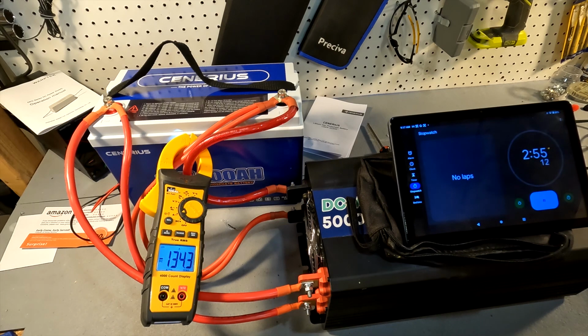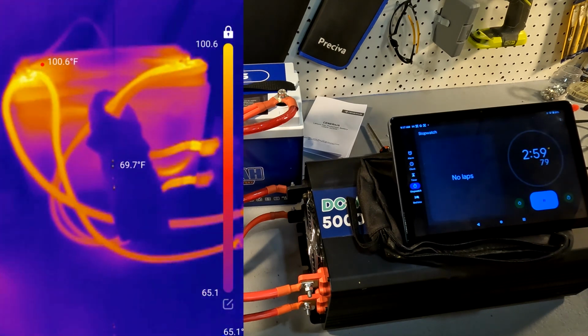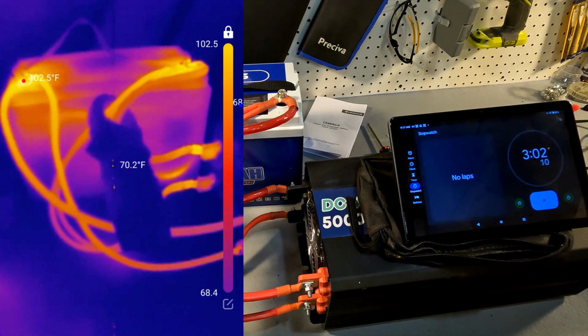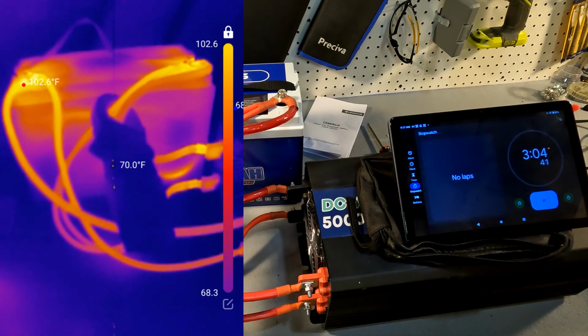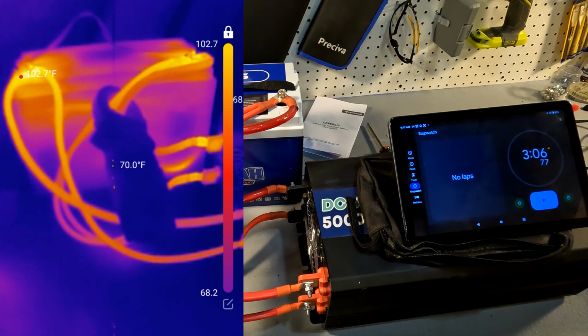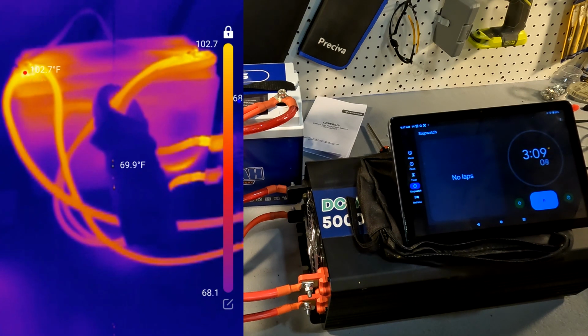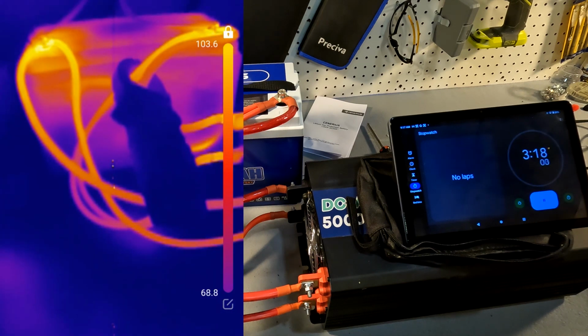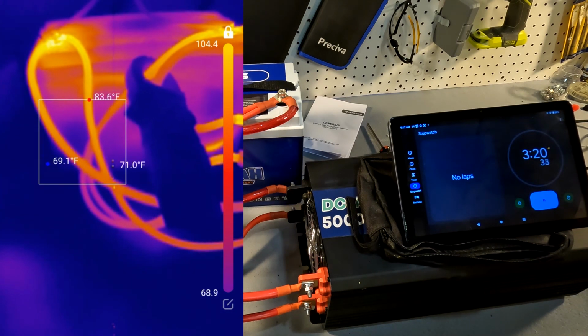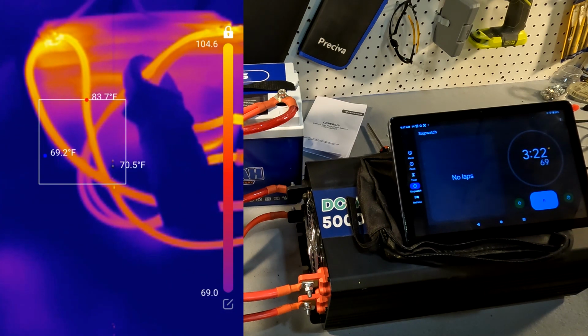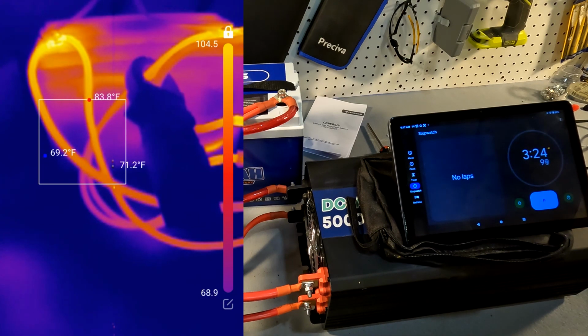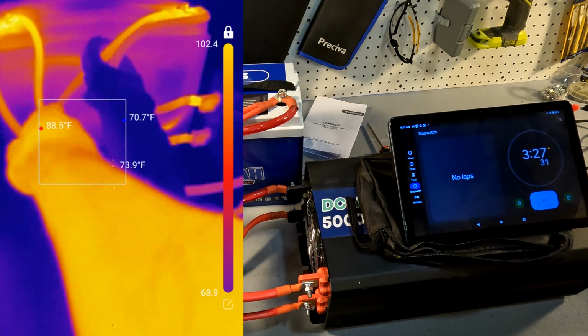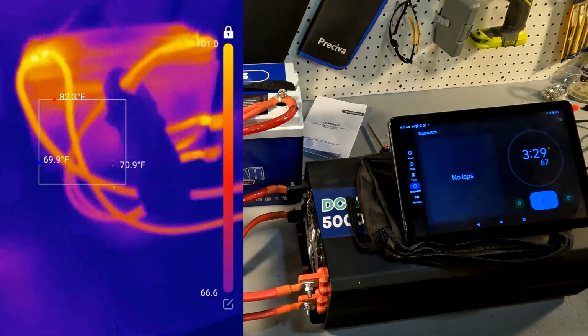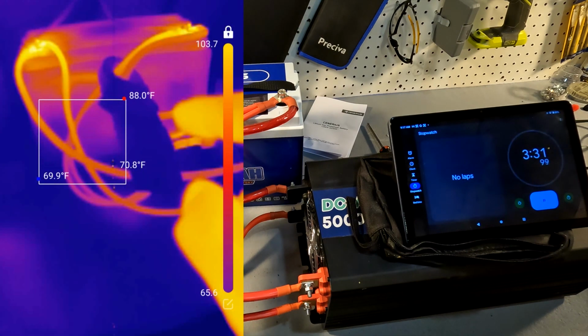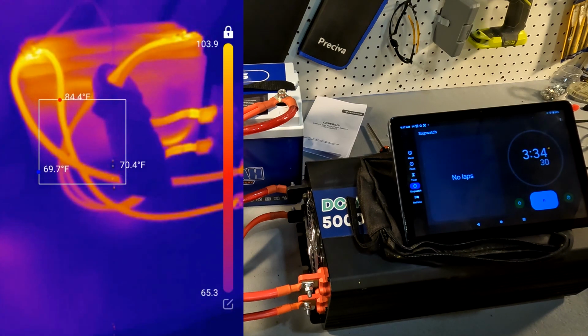All right, we are actually 3 minutes into this test, and we're looking at the battery on the thermal camera right now, and look at those terminals. You can see that the positive terminal, which is on the left, is running right at 102 degrees Fahrenheit. The cabling is cool, 83 degrees Fahrenheit, that is room temperature, not warm at all. That is the difference between proper cable sizing and improper cable sizing.